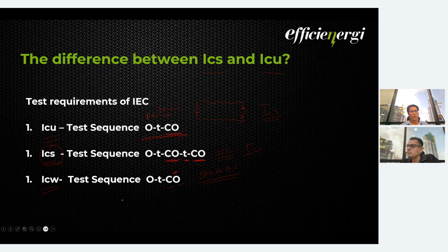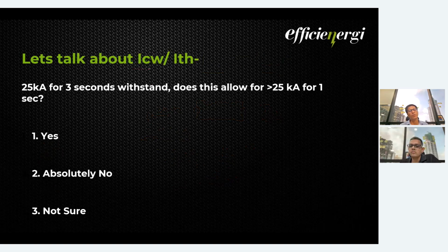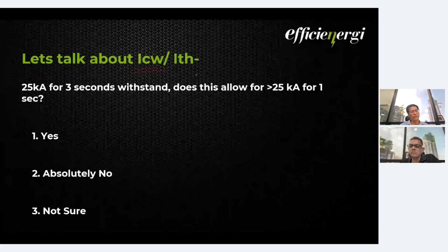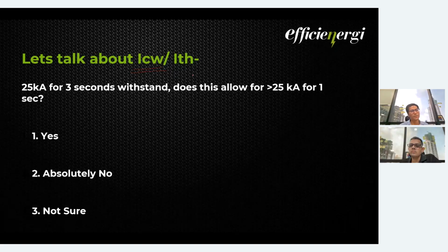Okay, now let's talk about the ICW. I think in most of these studies, people are not considering ICW at all. They are only concerned that my breaker is 50 kiloampere, my short circuit level at the bus is 45 kiloampere, less than 50 kiloampere. They say it is passed and we move forward and the device duty is clear. But this ICW is actually an important factor that should be included in the device duty reports.